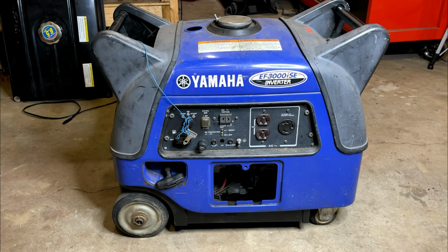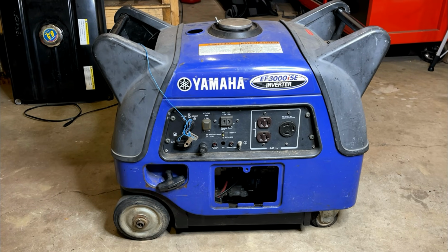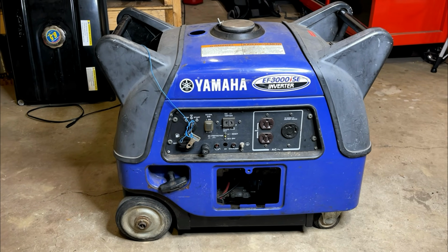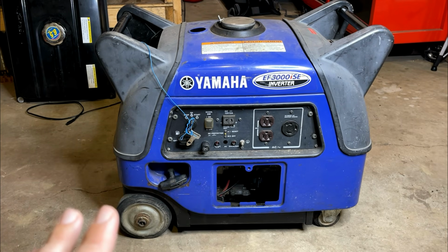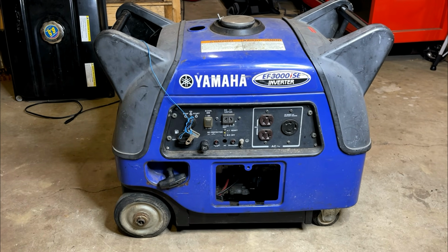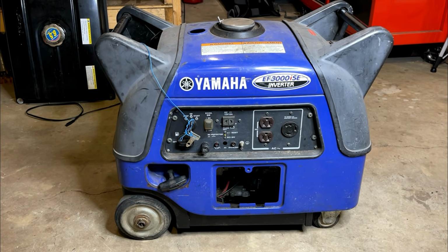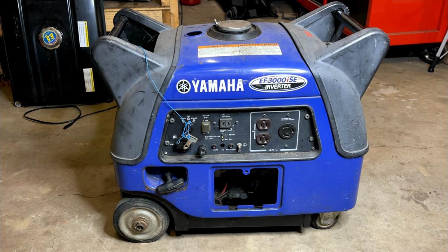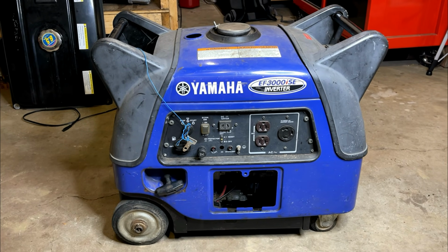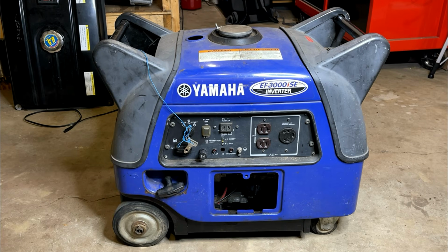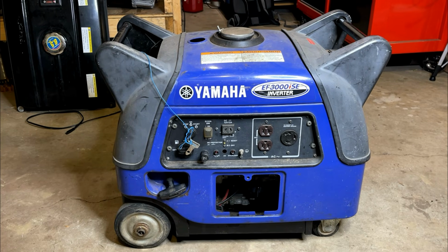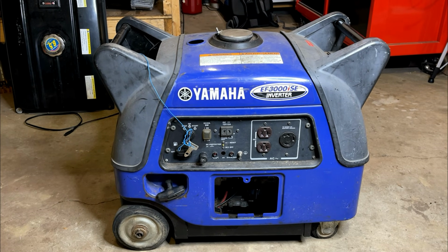I noticed a few things. The one time it made power, when it shut down, the eco switch became unresponsive and the overload light blinked just for a second. If the inverter was bad, I wouldn't expect it to be trying to make power, and I would expect that overload light to stay on constantly. So that's giving me a little bit of hope.